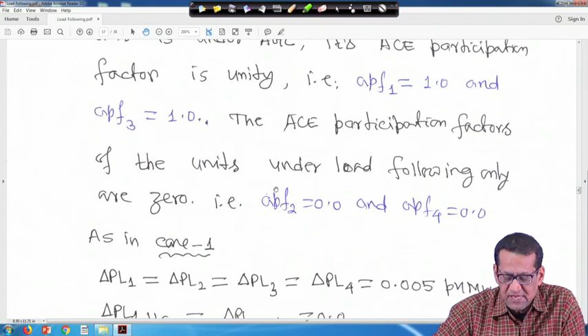As in case 1, the same data is taken: delta PL1 equals delta PL2 equals delta PL3 equals delta PL4, that is 0.005 per unit megawatt, and no uncontracted demand was there, so delta PL1 UC equals delta PL2 UC equals 0.0. Therefore, as we have seen earlier in steady state, delta PG1 SS will be 0.0, delta PG2 SS is 0.0085 per unit megawatt, because DPM remains the same. Uncontracted demand is not there, so delta PG3 SS will be 0.0 and delta PG4 SS will be 0.0115 per unit megawatt, same as before. Delta P tie 1-2 scheduled is also equal to minus 0.0015 per unit megawatt, right.